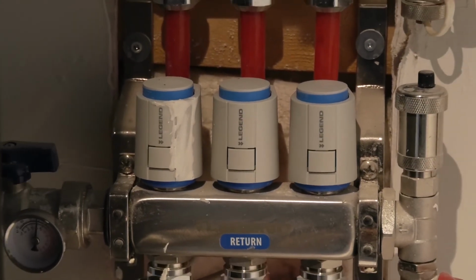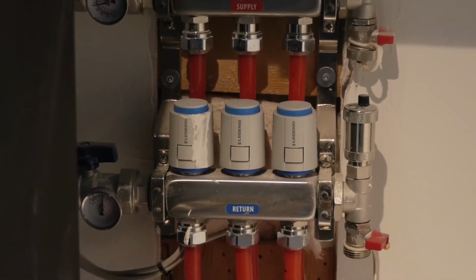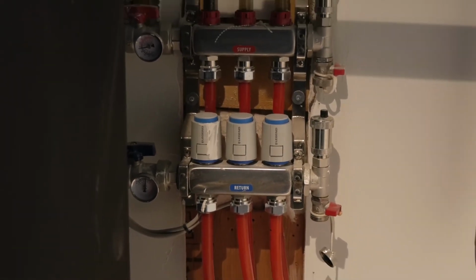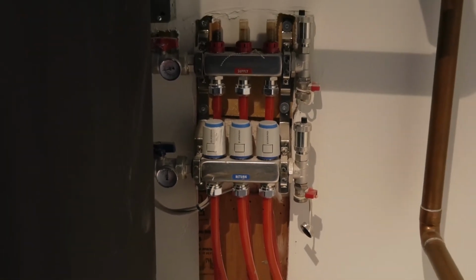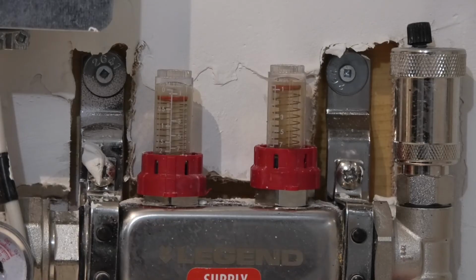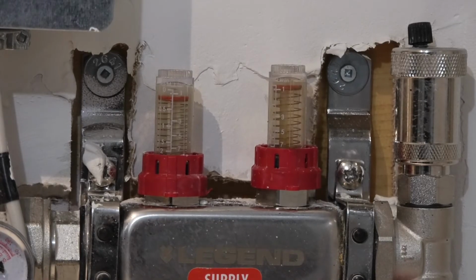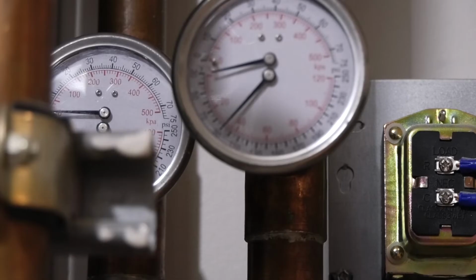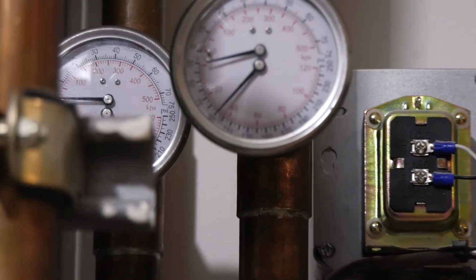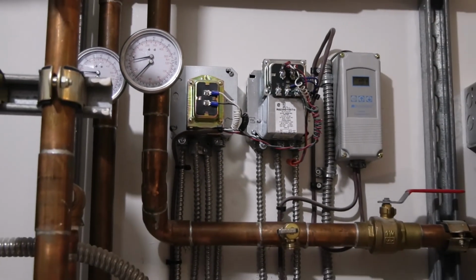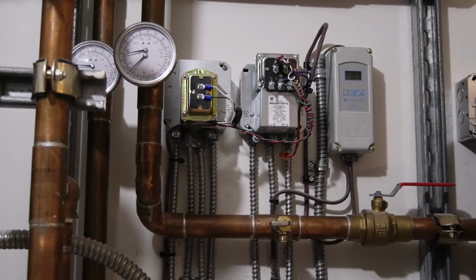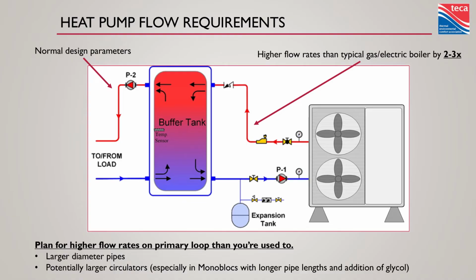But like I say, that buffer tank is interacting with the load at all times. So if this thing has been turned off while I was away vacationing and I come home and I turn on my heating system, all that water has to be warmed before any of that heated water gets out to those heat emitters to start heating the house, which slows the system down. If we're dealing with a thick floor slab that takes 8 hours to respond anyway, no one's going to notice. But like I say, if that's a fan coil, a panel rad, they are going to notice. That's where we use things like 3-port and 2-port buffer tank strategies.